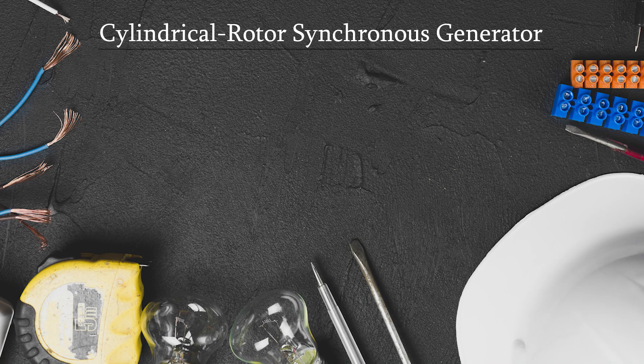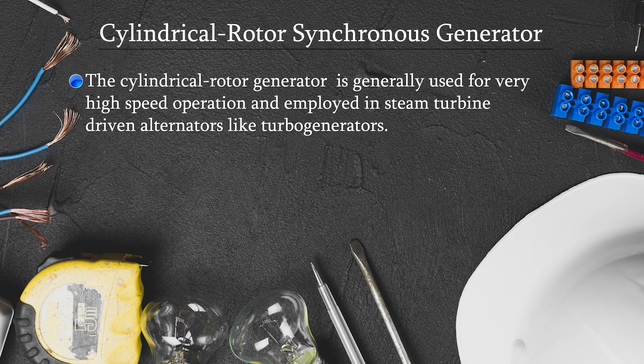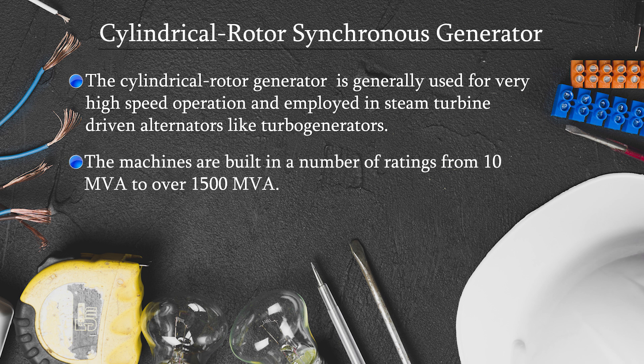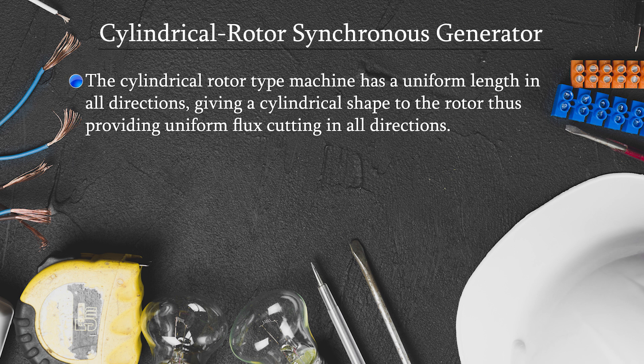Cylindrical rotor synchronous generator: this type is normally used for very high speed operation in steam turbine driven alternators, called turbo generators. Machines are built in different ratings, starting from 10 MVA up to 1500 MVA. The cylindrical rotor type has a uniform length in all directions, giving a cylindrical shape to the rotor and providing uniform flux cutting in all directions.